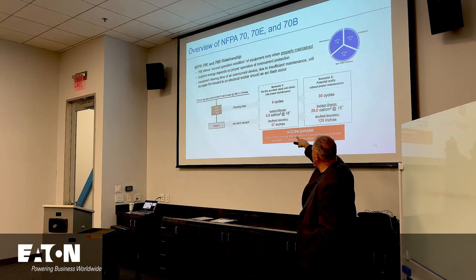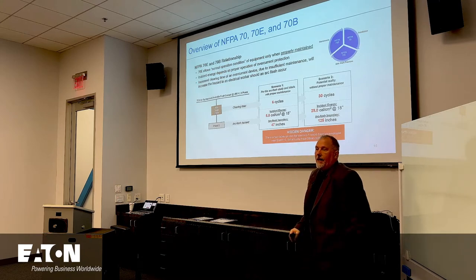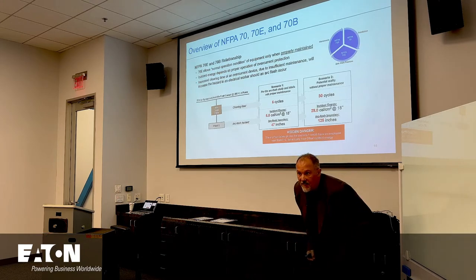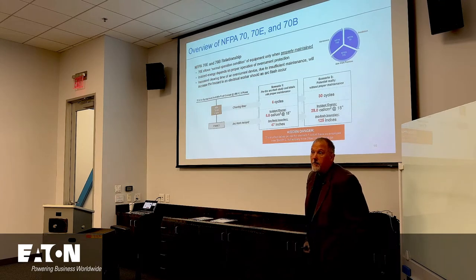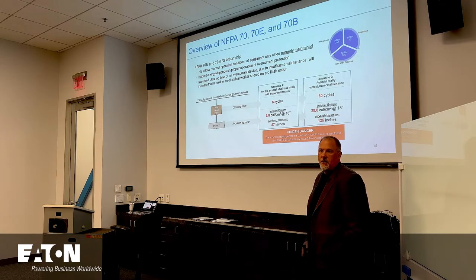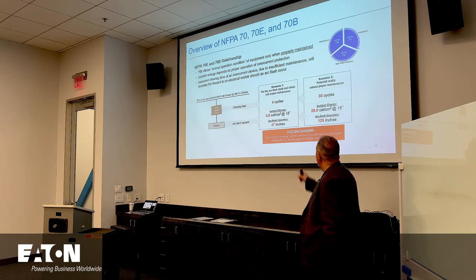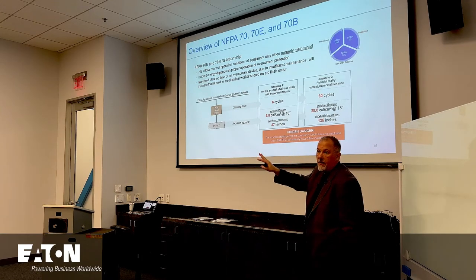I got 5.8 calories per centimeter squared. I still would not want to face 5.8 calories per centimeter squared, but it's dressable, right? Just wearing PPE, is that a guarantee you're not going to get killed or hurt? Absolutely not, right? It's like fall protection. If I had to use fall protection, I wouldn't want to use it, right? It's not a guarantee you're not going to get killed or hurt severely. In a lot of these cases, you've got shrapnel and everything else coming out.